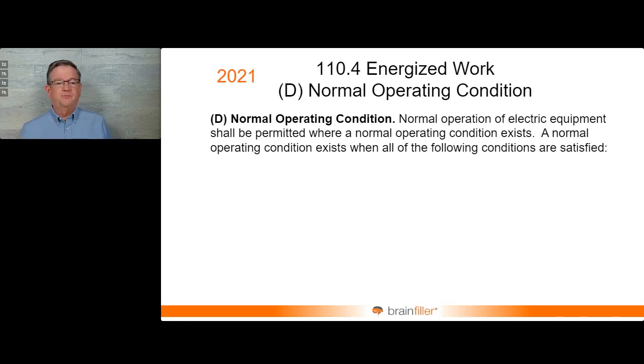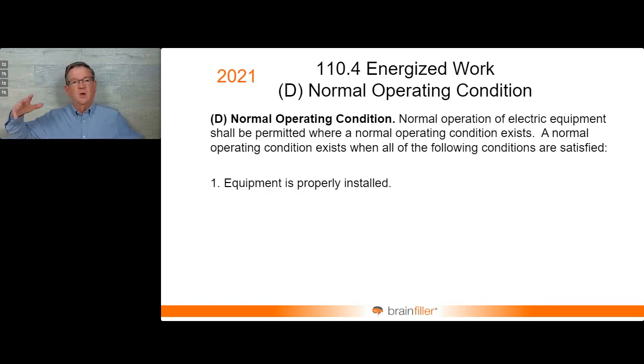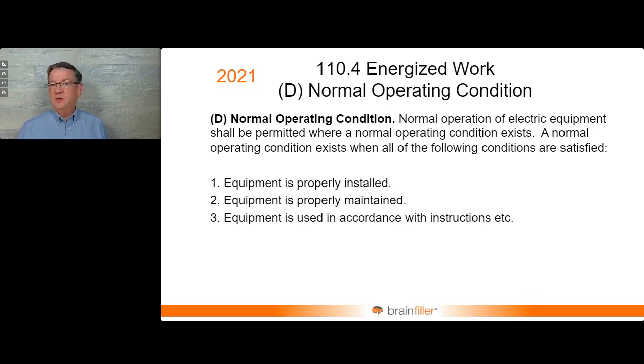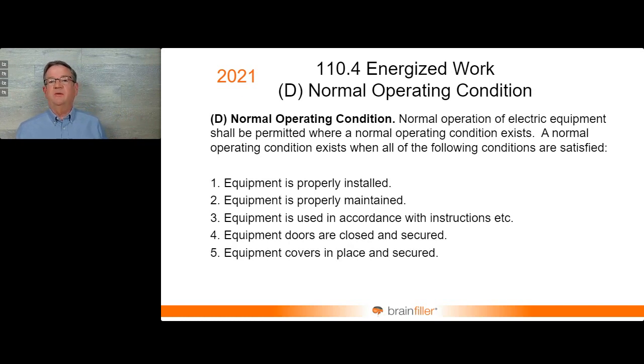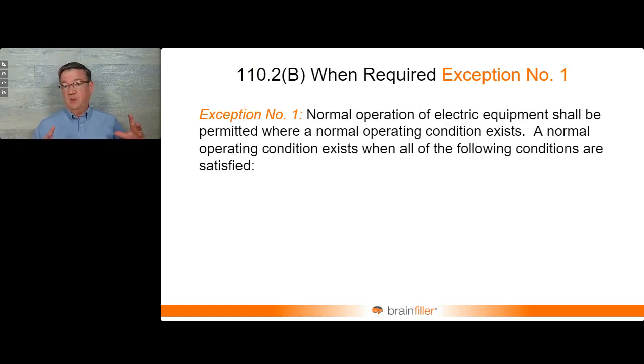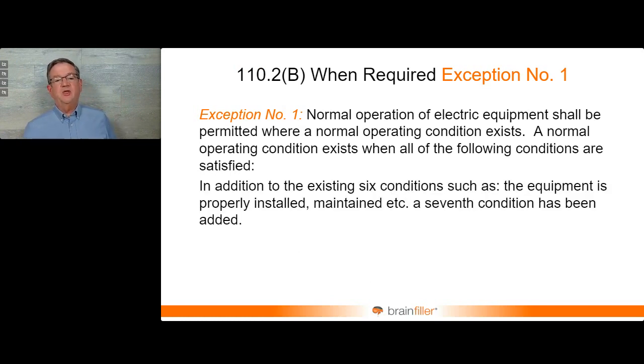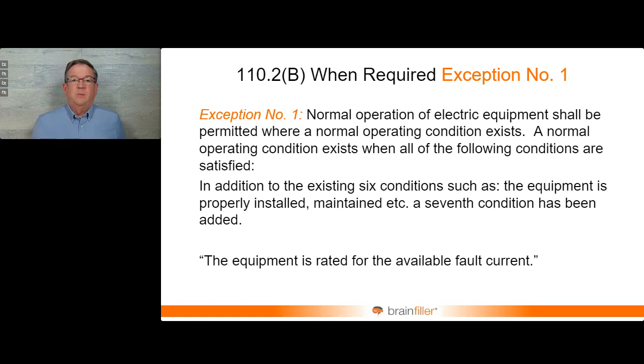Normal operating condition, this is what we had back in 2021. And we had 6 items, check the boxes. If the equipment is in a normal operating condition, it was thought, okay, there's not really much of a risk of an arc flash hazard. And so checking the boxes: has the equipment been properly installed, properly maintained, used in accordance with the instructions, equipment doors closed and secured, covers in place, no evidence of impending failure. And that's what we've had. We have a relocation. This is now an exception. So the 6 boxes to check are still there, but they're part of an exception, and we have a 7th item. And the 7th item is to make sure that the equipment is rated for the available fault current.